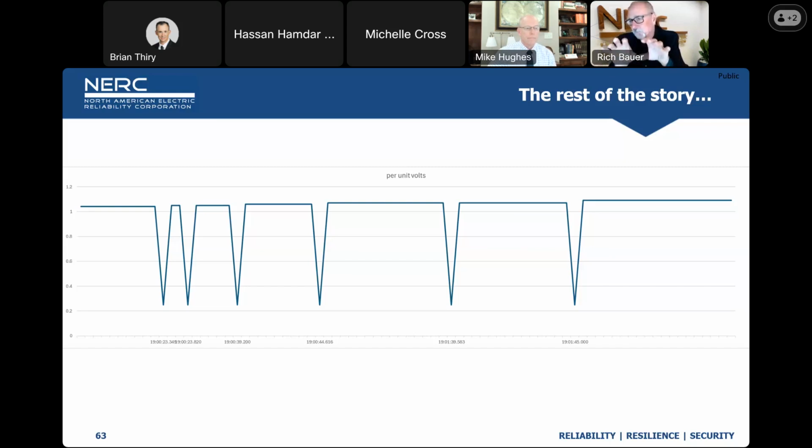So we basically gave the data centers 3 voltage dips within about 25 seconds. So they told us that they would lock out after 3 disturbances within 60 seconds. So we definitely did that. So we can go to the next slide, Mike.